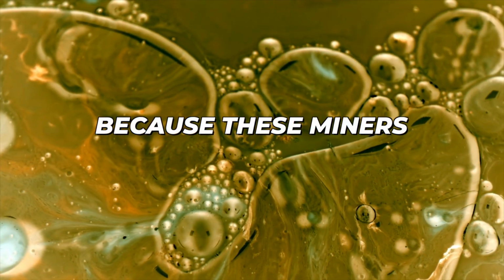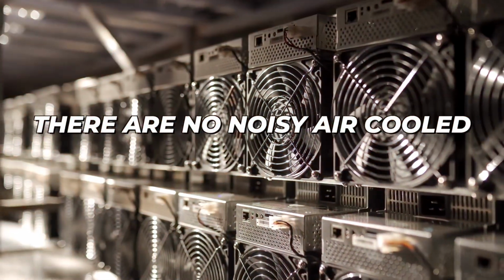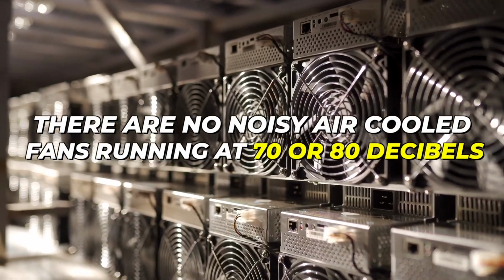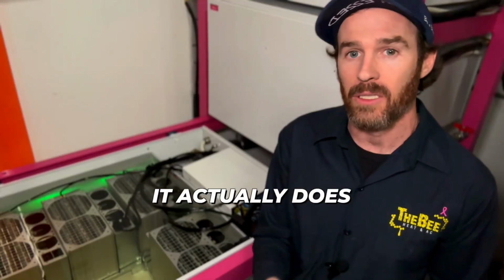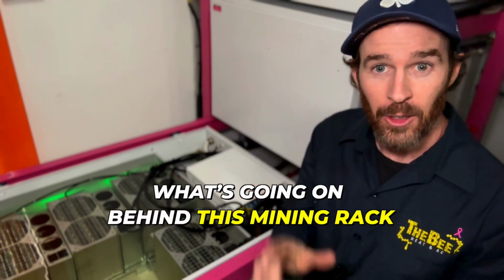The reason our miners are set up this way is primarily to mine Bitcoin more effectively, cooling the equipment down and also much quieter. Because they're submerged in fluid, there are no noisy air-cooled fans running at 70 or 80 decibels, and it actually cools the miners better and keeps them in better shape with less dust and contaminants than normal air cooling. This way we use the heat and repurpose it to heat our office, which I'll show you now.